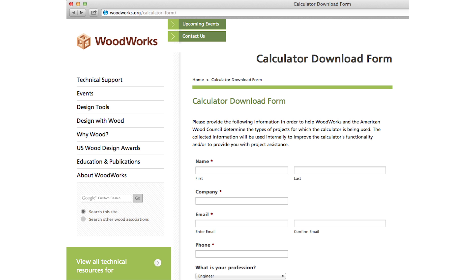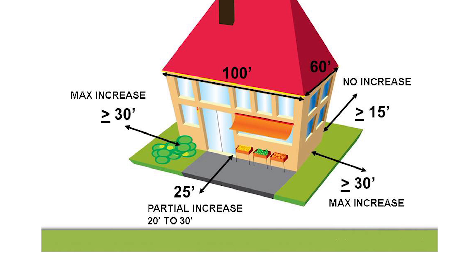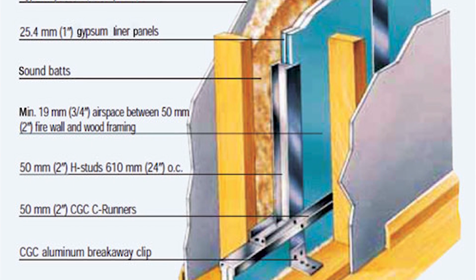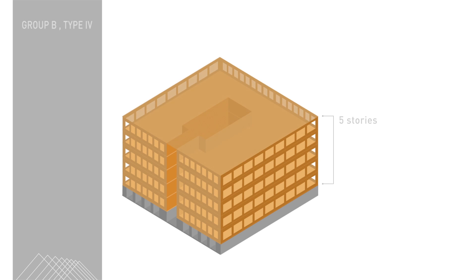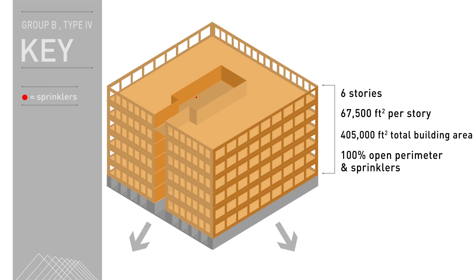Sprinklers allow you to go one story higher and also increase your square footage within the building. For Type 3, Type 4, and Type 5 construction, you can increase your square footage based on the amount of open area around the building — this is called a frontage modification increase. Another way to increase your area is by adding firewalls, because the code treats a firewall as creating two separate buildings, allowing a larger overall footprint. Combined with sprinklers and open frontage modifications, you can effectively triple your square footage.